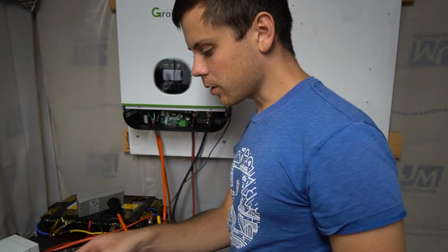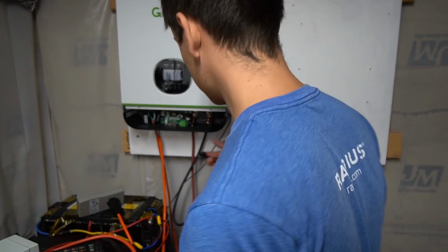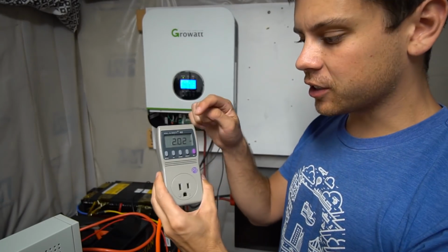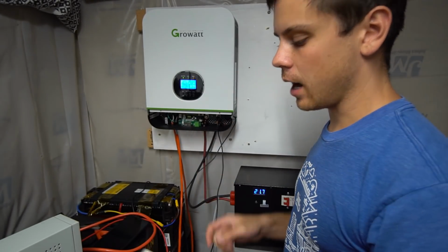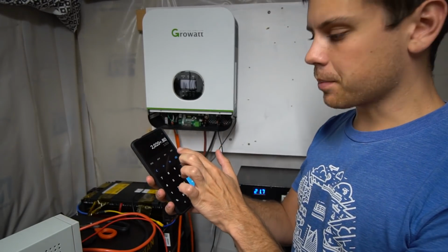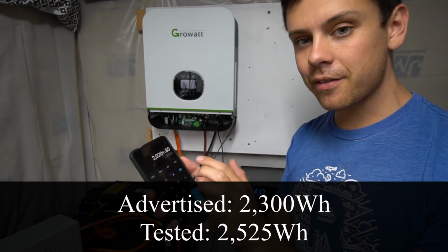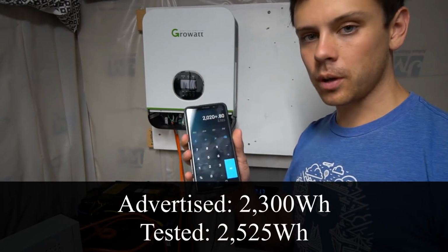The test is over and we need to turn it back on again to see the results. So the final test result is 2.02 kilowatt hours. The inverter efficiency is 80%, so we pulled 2.5 kilowatt hours—it passed this test.